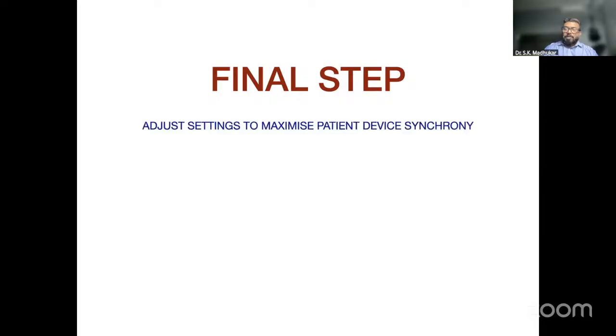Last step, where we all have very scarce literature. We don't have much access to all the finer points. So last step in the ventilator setting, and this last step is important to maximize the patient device synchrony. You have set everything, but if your patient is not synchronized with the device, your NIV is going to fail.